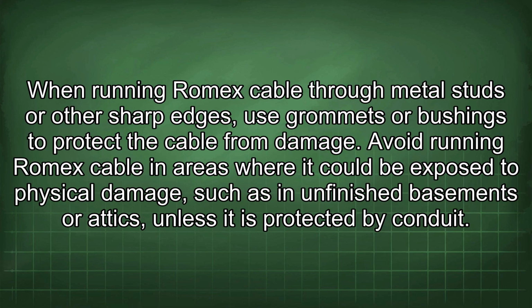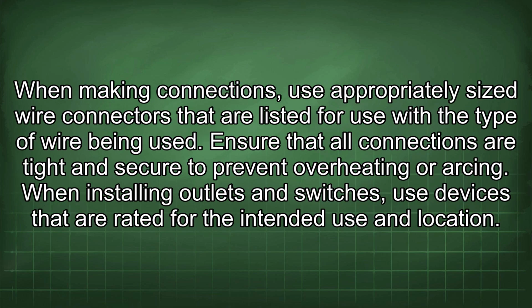When running Romex cable through metal studs or other sharp edges, use grommets or bushings to protect the cable from damage. Avoid running Romex cable in areas where it could be exposed to physical damage, such as in unfinished basements or attics, unless it is protected by conduit. When making connections, use appropriately sized wire connectors that are listed for use with the type of wire being used. Ensure that all connections are tight and secure to prevent overheating or arcing.